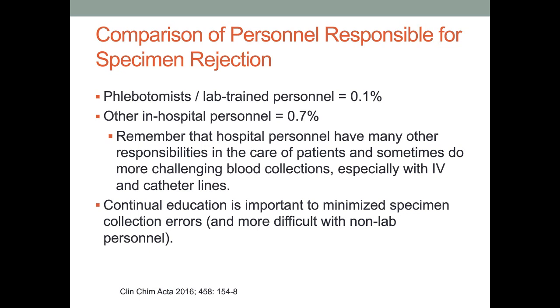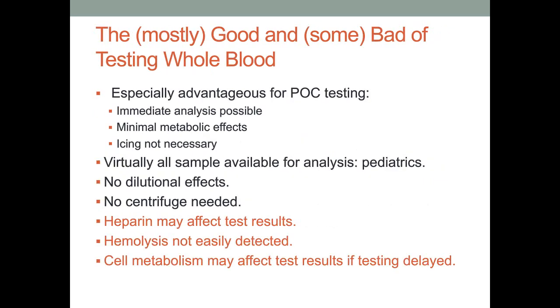For blood gas analyzers and point-of-care testing, we use whole blood. This is especially advantageous: immediate analysis is possible without centrifugation, there are minimal metabolic effects if the sample is analyzed quickly, icing is not necessary, and for pediatric applications you can analyze virtually all of the available sample. There are no dilutional effects as seen with some electrolytes measured on large chemistry analyzers. Some disadvantages include that heparin may affect test results, hemolysis is not easily detected in whole blood, and cell metabolism may affect test results if testing is delayed.